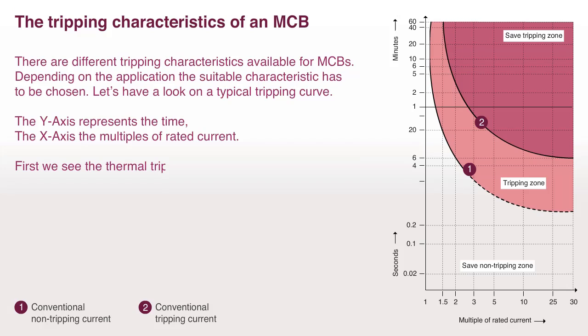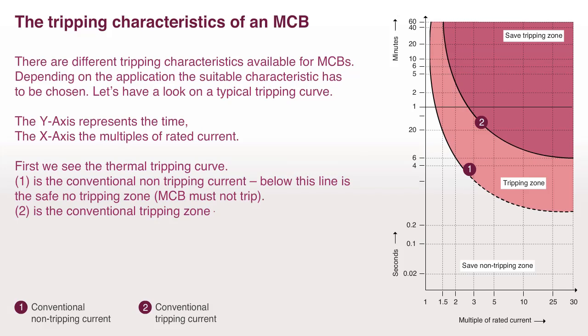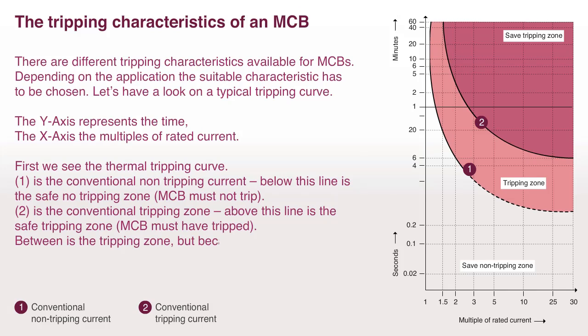First we see the thermal tripping curve. One is the conventional non-tripping current. Below this line is the safe no-tripping zone — the MCB must not trip. Two is the conventional tripping zone. Above this line is the safe tripping zone — the MCB must have tripped. Between is the tripping zone, but because of variances, it is a zone and not a fixed value.